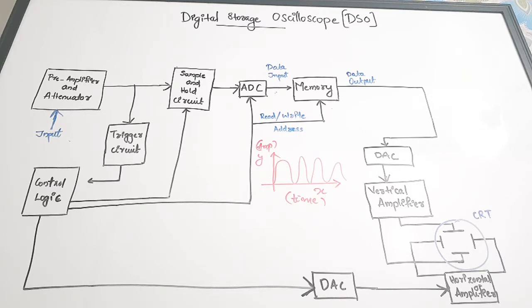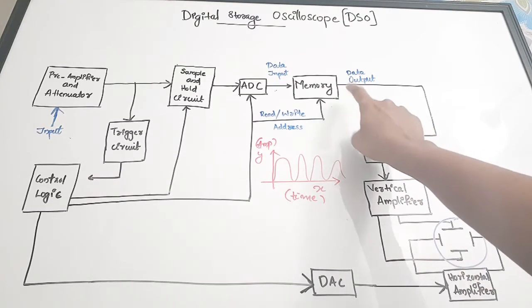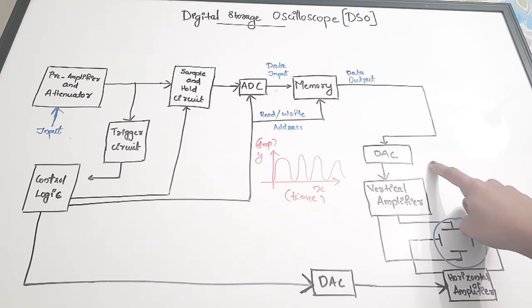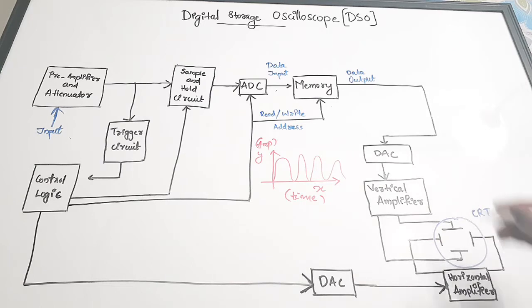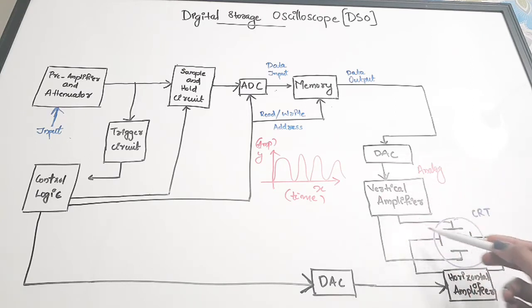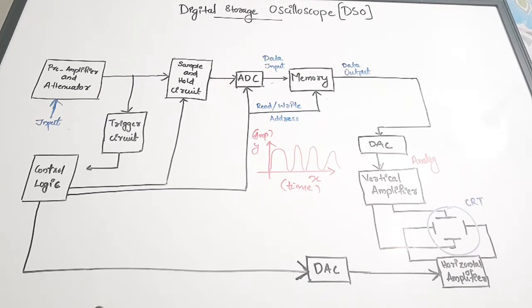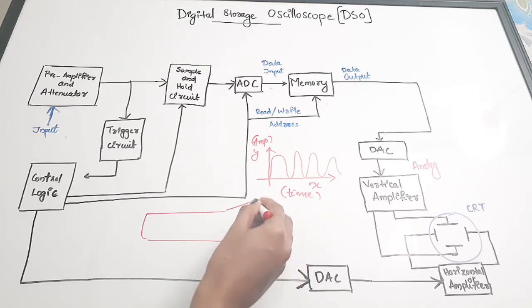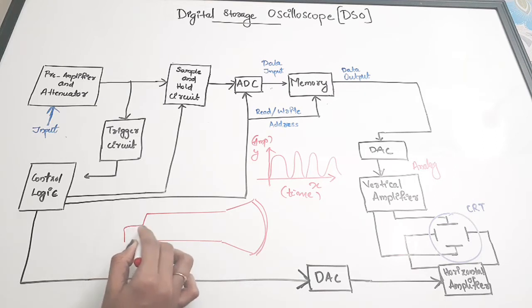The data is stored in digital format. We also have to display the data on a screen, showing the same waveform we are feeding. If you are feeding a sine wave, we don't require digital form display but the exact sine wave itself. So the digital data is taken from memory - data output - and given to a D-to-A converter. It will be converted back to analog form, and this output will be analog. It is then given to the vertical amplifier and to the CRT - the cathode ray tube.